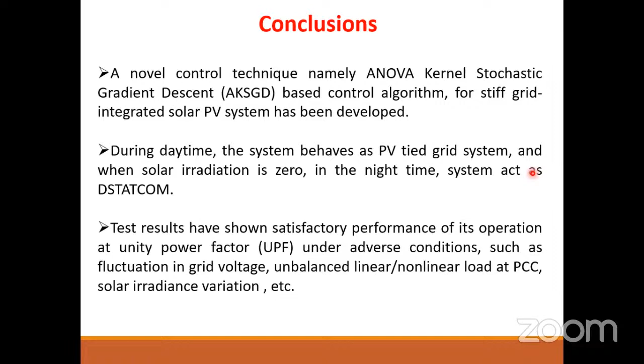But at the same time, suppose you don't have any load and are directly attached to the grid. Then grid voltage estimation becomes a serious issue. Based on the voltage estimation, you decide the amount of reactive power according to the filter's capability, and then generate that reactive power to feed into the grid. Of course, the grid is large, so we cannot generate hundreds of MVAR and feed it in. But according to your inverter's capability, you can generate reactive power and support the grid in night mode or day mode as well.